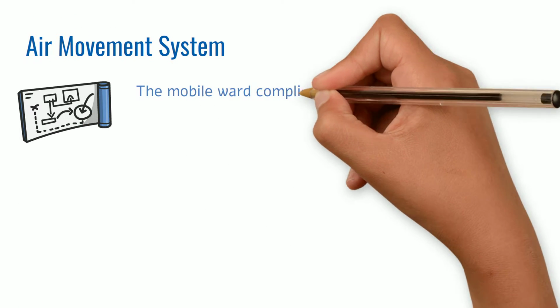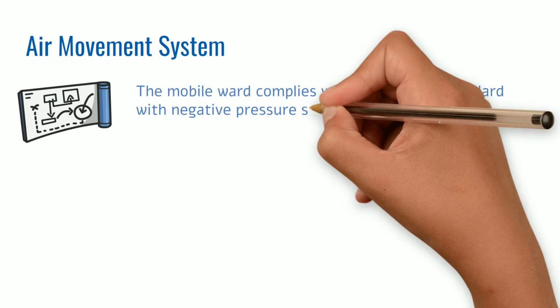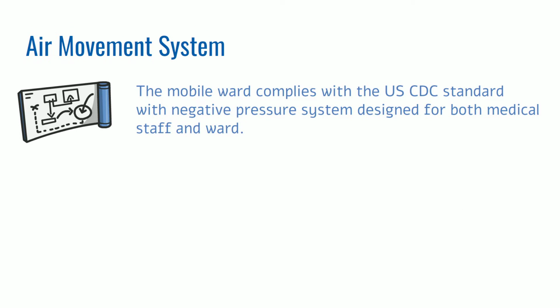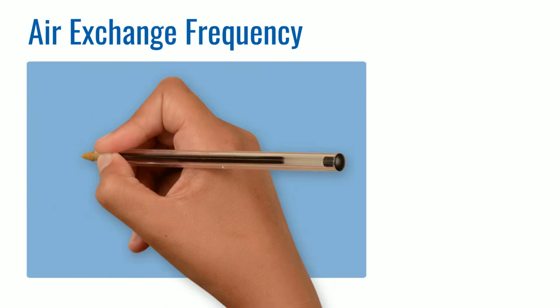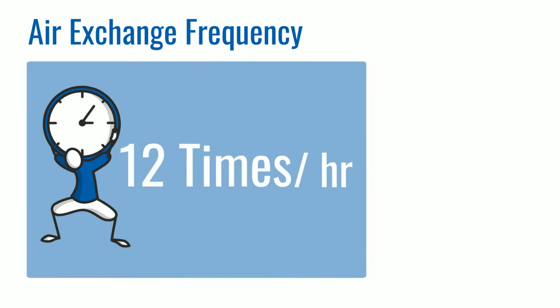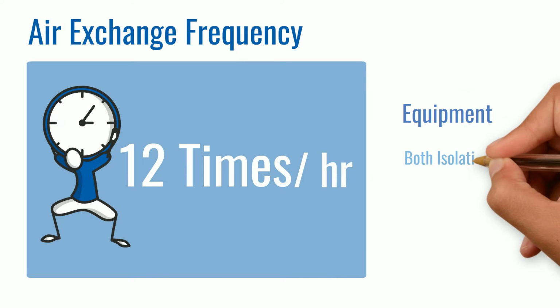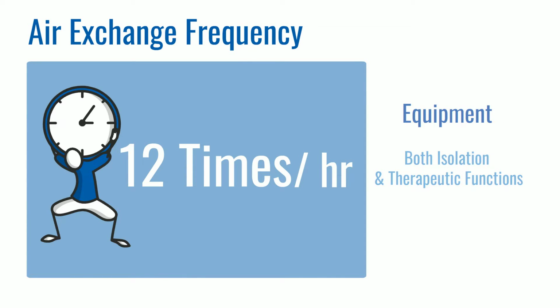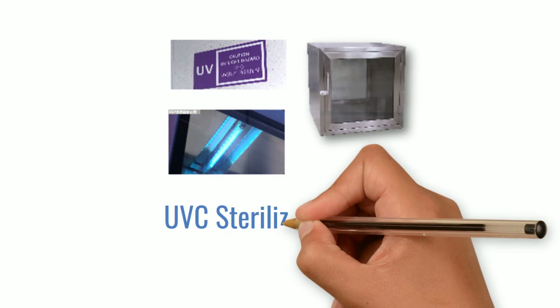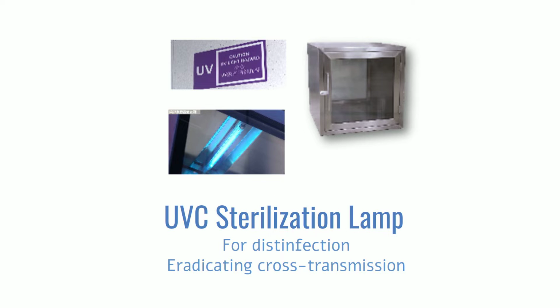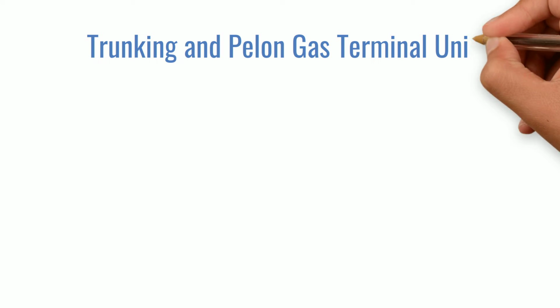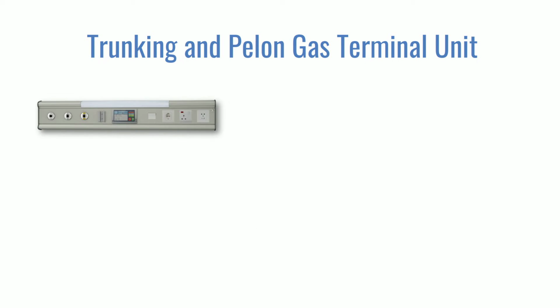Another high specification feature is that an air movement system is set up in the ward. The mobile ward complies with the US CDC standard, with a negative pressure system designed for both medical staff and ward. There are fresh air replacements 12 times every hour with medical gas outlets, and it is equipped with both isolation and therapeutic functions. All delivery of external supplies would pass through a UVC sterilization lamp for disinfection, eradicating cross-transmission. Simultaneously, trunking and Penlon gas terminal unit is also a special highlight.